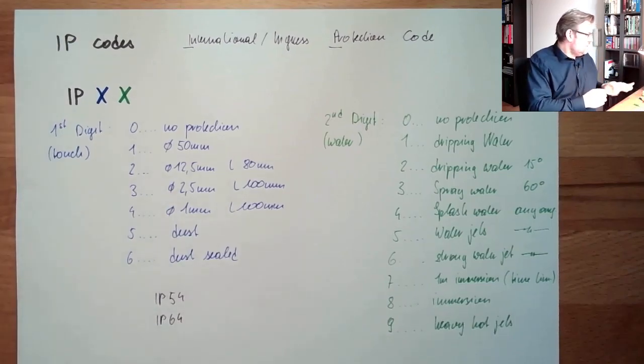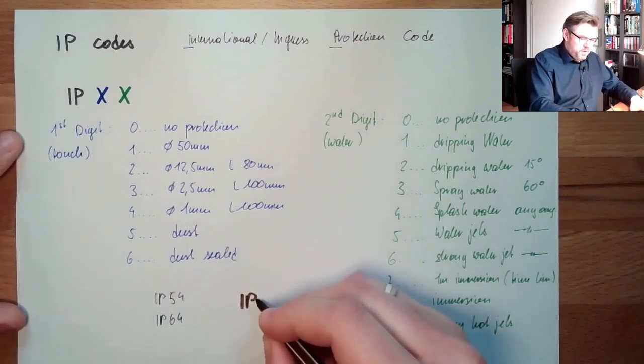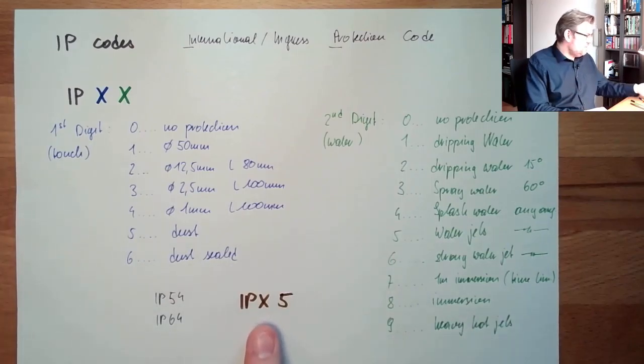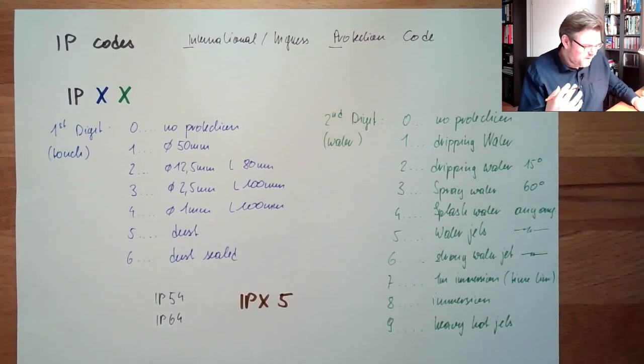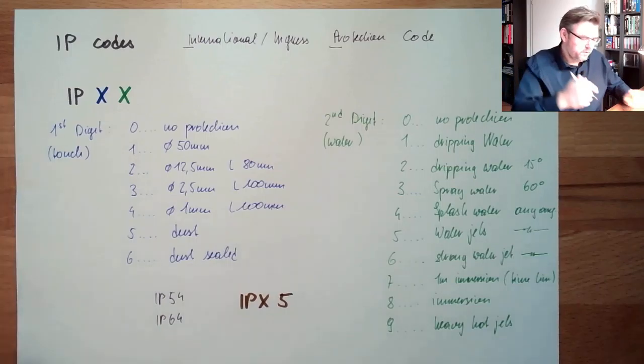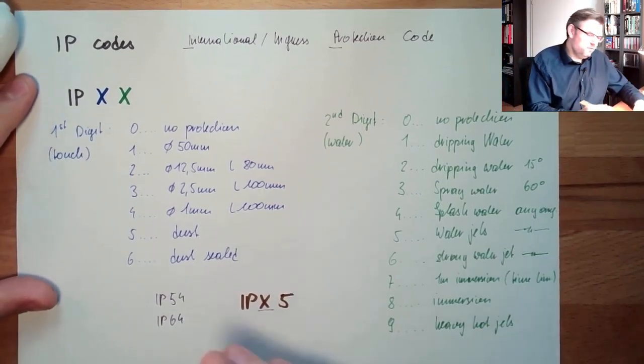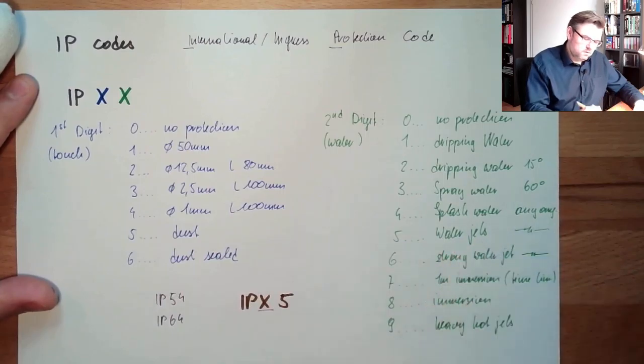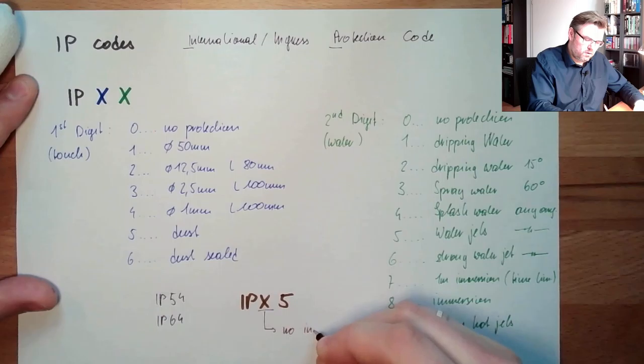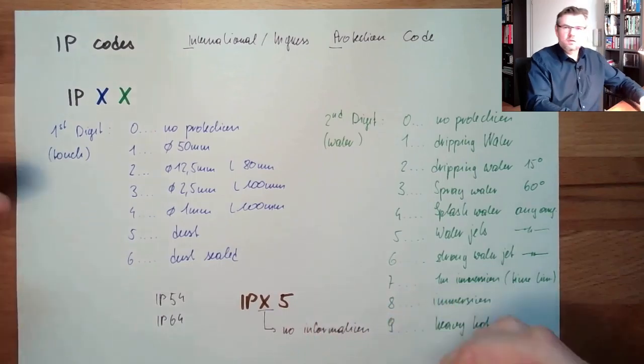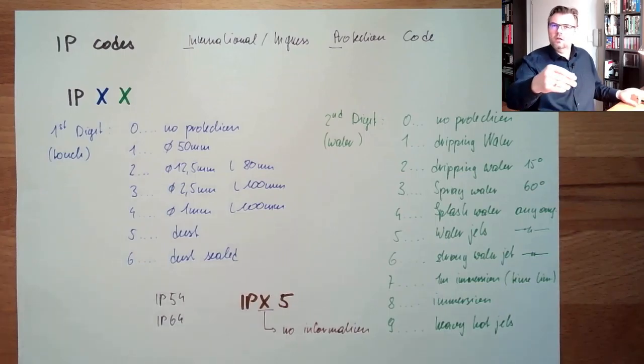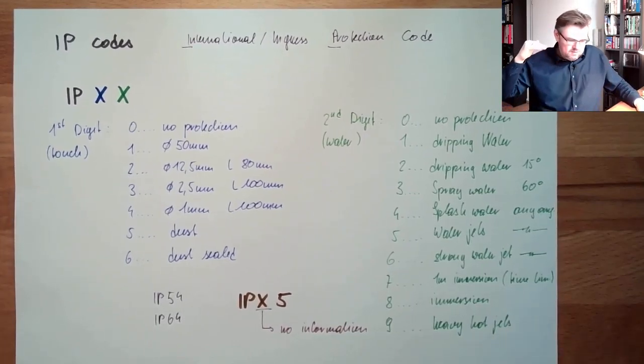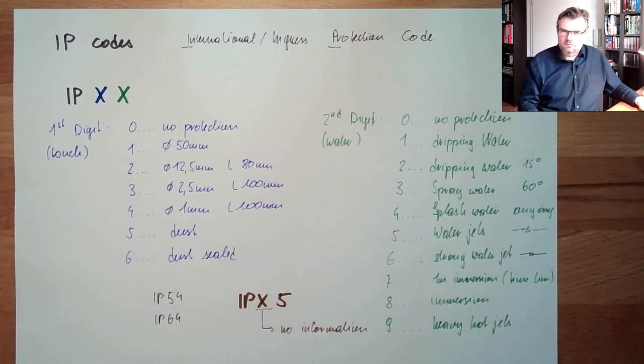Sometimes you see that there is written IPX5. And this X makes it look even more fancy than just IP. However, you know, this X here only means it's not defined. The first letter, there is no information given about the protection against touching, only against water. So this means nothing. This simply means no info. So it's not particularly fancy. It's just I'm not going to tell you. It's already sound a little bit with tendency. It maybe means it's not really important.